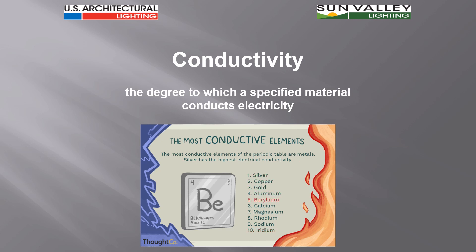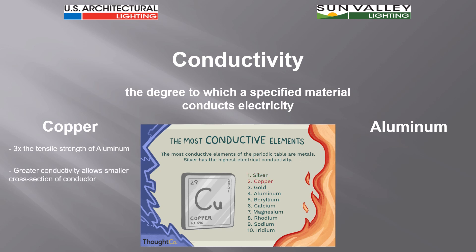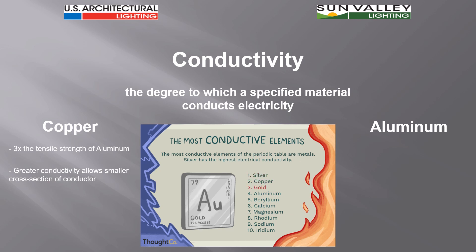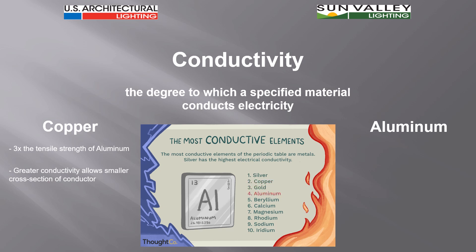Copper is what we see in most instances. First, copper has three times the tensile strength of aluminum — it's a much tougher material when pulling it end to end, easy to pull through conduit, and doesn't want to break. It is heavier, so that comes into play later. But its greater conductivity allows a smaller cross-section, so we can use a lighter or smaller gauge of copper wire to carry a specified amount of current versus what we'd need with aluminum.